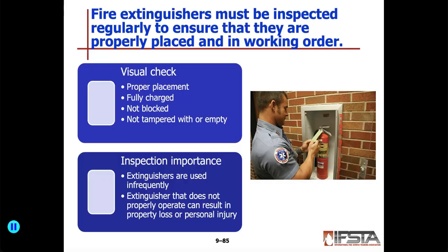Your visual check is going to include: is it placed properly? Is it fully charged? You should be able to see that on the dial. Is it blocked? Or is it tampered with? Or is it empty? Right?